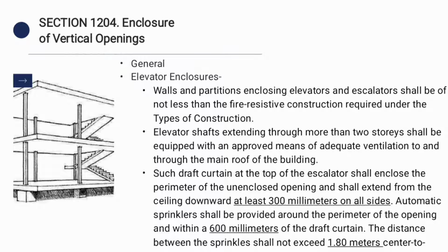So ang enclosures dili na kayo required sa mga escalators, diraan na mga types sa occupancies. And then provided sad na sa top sa imuhang escalator naa siya in each story kay naa siya kanang natawag nato nga draft curtain. This draft curtain shall enclose the perimeter of the unenclosed opening and shall extend from the ceiling downward at least 300 millimeters on all sides.